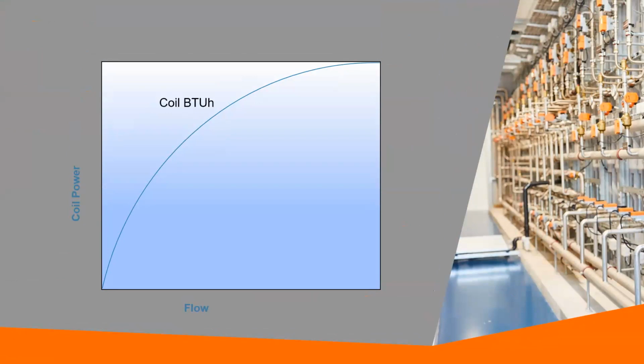Note that the coil curve is not linear. At that low flow rate, each molecule of water spends a long time in the coil, and it absorbs a proportionally large amount of heat. So small increases in flow make large increases in heat transfer. This is why that curve is steep at low flow, and at high flow rates, the curve starts to flatten. And this is because each molecule of water only spends a short amount of time in that coil. So many more are needed to increase that heat transfer rate.